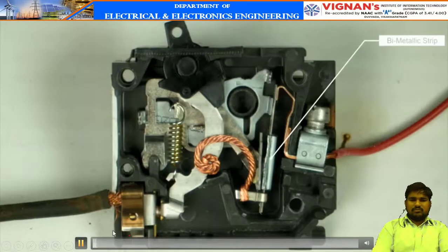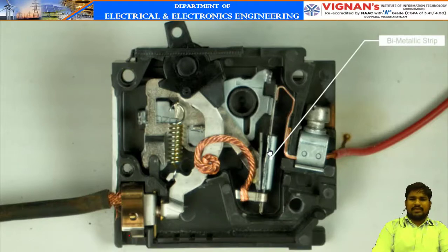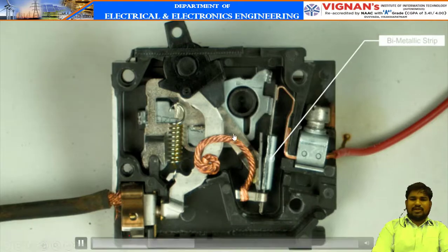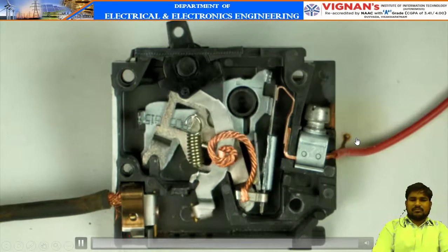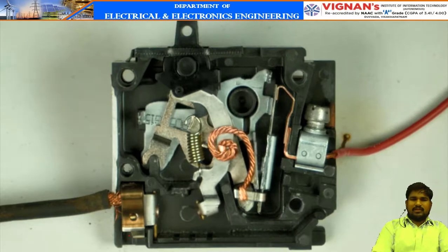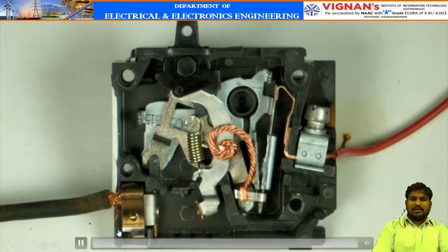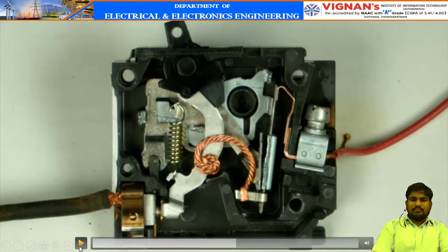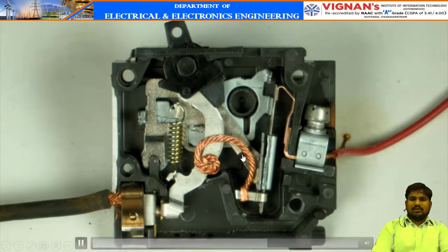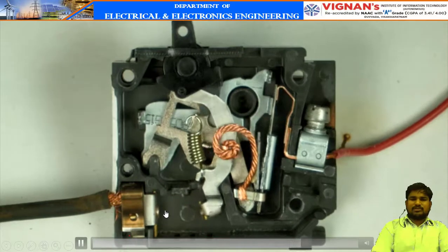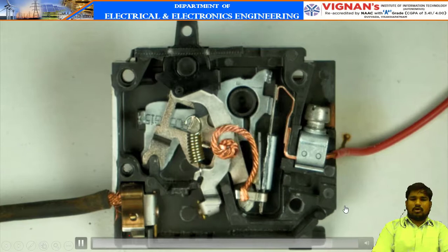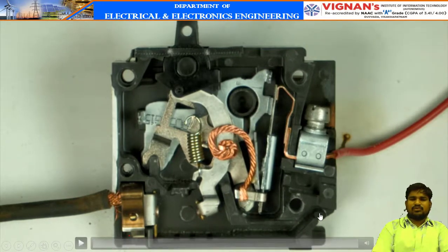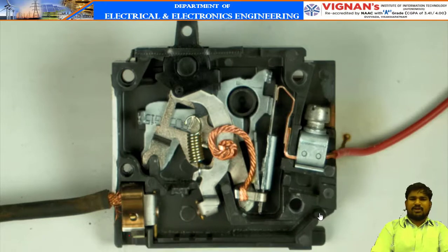Now, this is the bimetallic strip. During overloading conditions the bimetallic strip expands, or during faulty conditions, because of this magnetic coil, the strip will be pulled out. Hence, the contacts will be separated with the help of this actuating mechanism. You can observe here, the strip was pulled and there is a separation of contacts. Because of that magnetic pull, the actuating quantity helps to separate these two contacts. To quench the arc generated between the contacts, we use an arc chute, right? So this is the operation of the miniature circuit breaker.